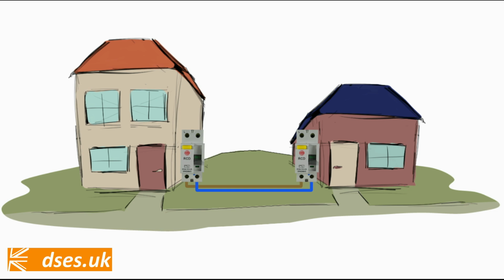In the event of an earth fault on a final circuit here, one or both RCDs may trip and all bets are off as to which may react the quickest. It's not necessarily the one closest to the fault. Ambient temperature, tiny variations in component tolerances and manufacturing, moisture levels and foreign particles are all examples of factors that affect the reaction time when these things need to mechanically operate.